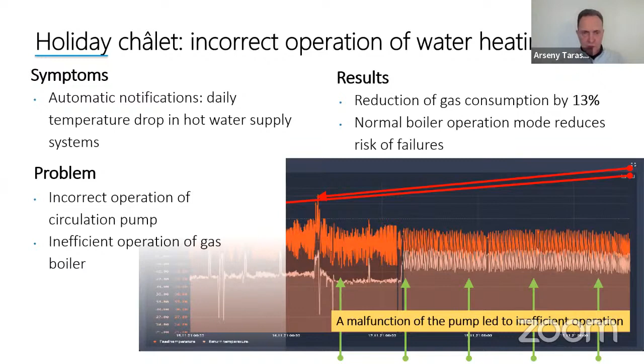Every morning at 7 o'clock, the system would start giving a notification that something was wrong with the water temperature. It turned out that because of a problem with one of the circulation pumps, the gas boiler worked in an incorrect mode. You can see this is not right - not healthy for the gas boiler. When we looked at the issue, we reprogrammed and replaced this circulation pump, which led to a 13% decrease in gas consumption, and also much healthier and safer operation of the boiler, meaning much lower risk of failures in the future.